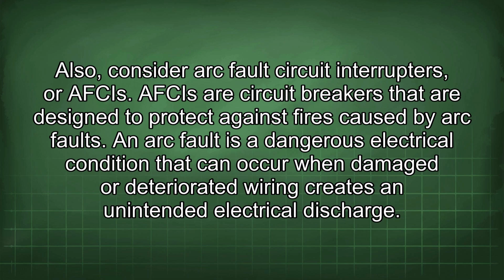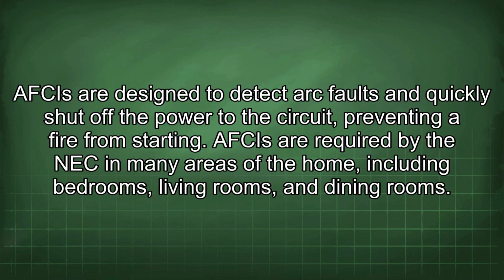Also, consider arc fault circuit interrupters, or AFCIs. AFCIs are circuit breakers that are designed to protect against fires caused by arc faults. An arc fault is a dangerous electrical condition that can occur when damaged or deteriorated wiring creates an unintended electrical discharge.